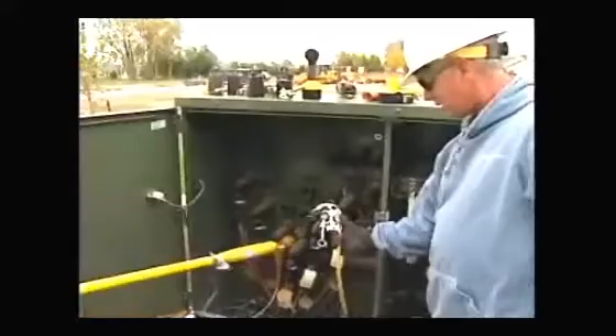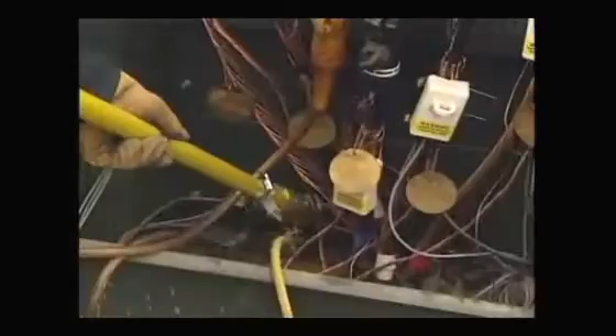Okay, what we're going to do now is Vince and I are going to take these phase sticks, and this will tell us definitely that these cables are de-energized. That one's de-energized, and that one's de-energized. If we would put a ground on one of these cables that was energized, made that mistake, we would have a heck of a ball of fire.